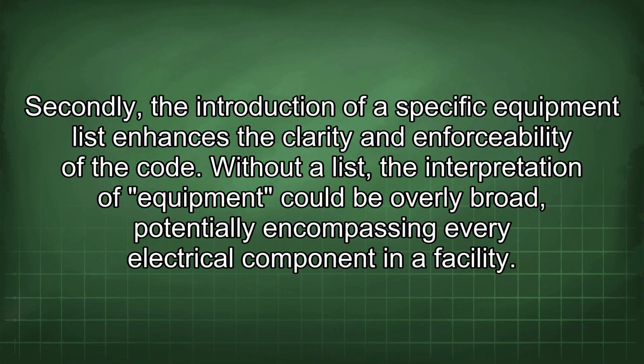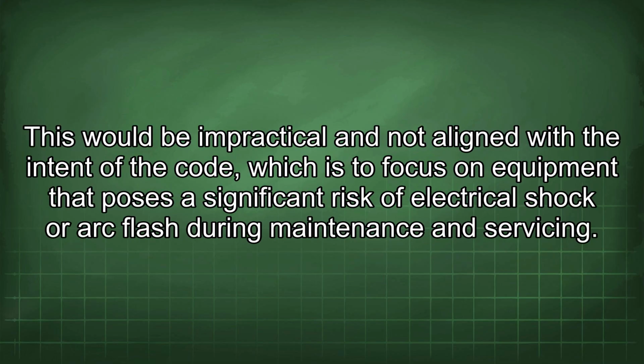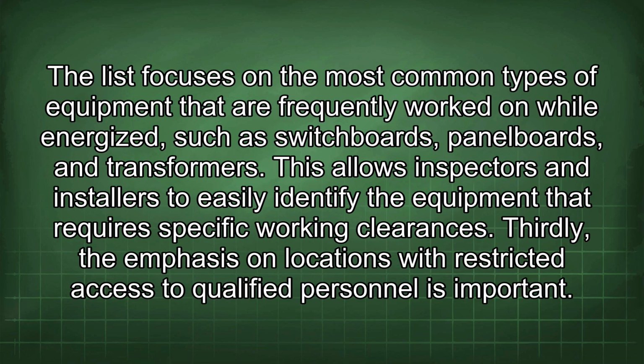Secondly, the introduction of a specific equipment list enhances the clarity and enforceability of the code. Without a list, the interpretation of equipment could be overly broad, potentially encompassing every electrical component in a facility. This would be impractical and not aligned with the intent of the code, which is to focus on equipment that poses a significant risk of electrical shock or arc flash during maintenance and servicing. The list focuses on the most common types of equipment that are frequently worked on while energized, such as switchboards, panel boards, and transformers. This allows inspectors and installers to easily identify the equipment that requires specific working clearances.